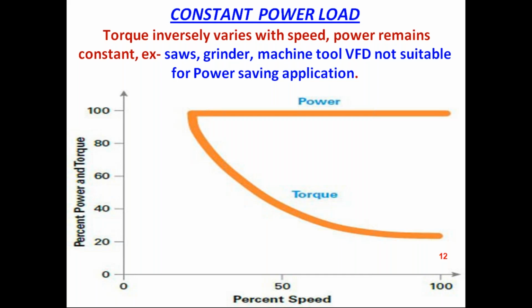If it is metal working machines or equipment, where we find electric saws, grinders or machine tools, a VFD is not suitable for this type of application, and it will not give power savings either. The power is always constant for any amount of speed, and the torque is very high only initially and starts reducing as the speed increases.